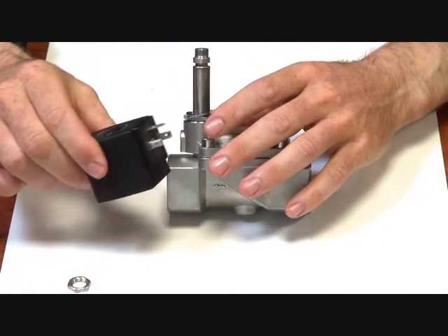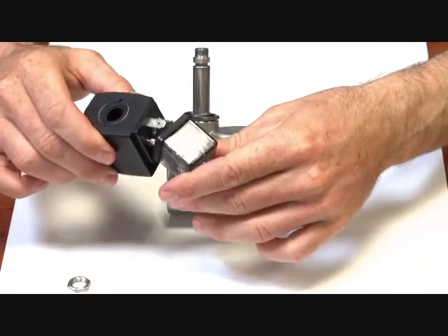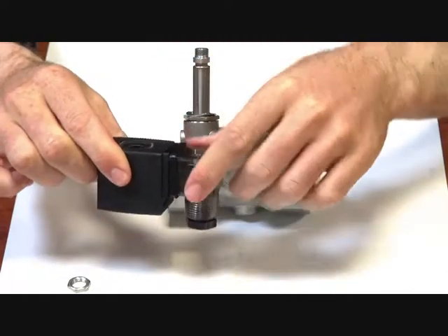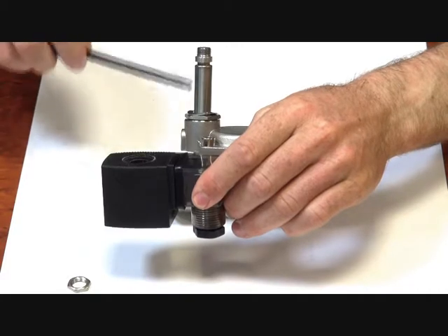So this is the coil, it's the part which obviously you hook the power up to if you want to install this valve, and power goes to it, it creates an electromagnetic force within here, which lifts the armature up in the operator stem.